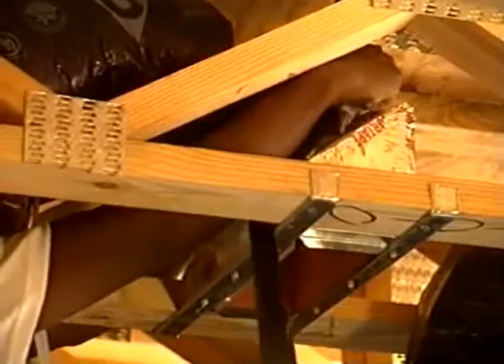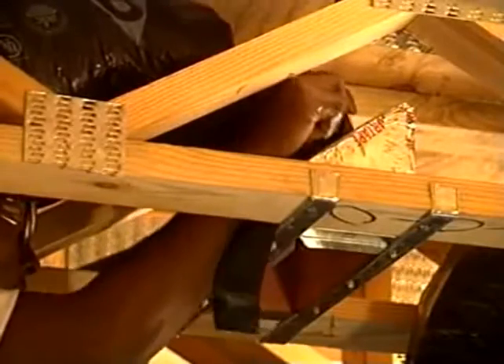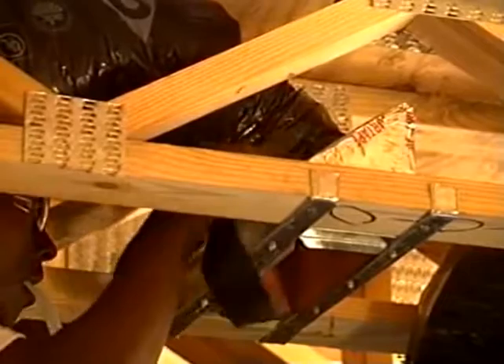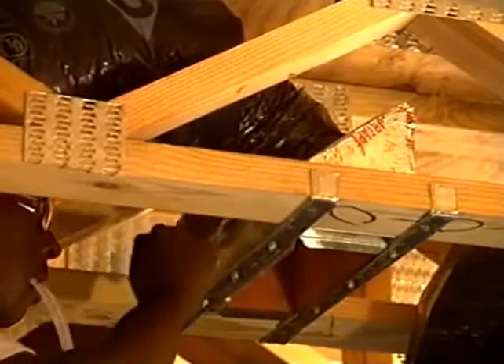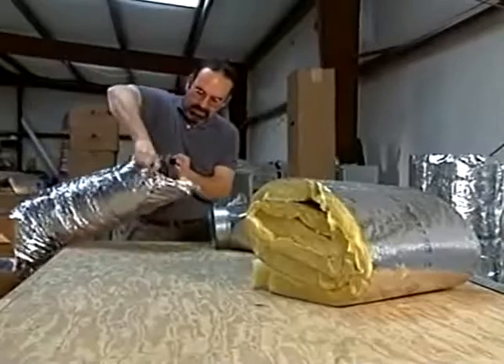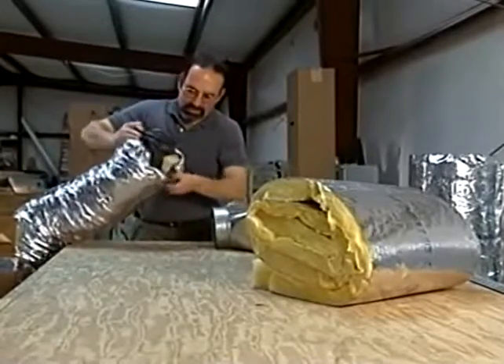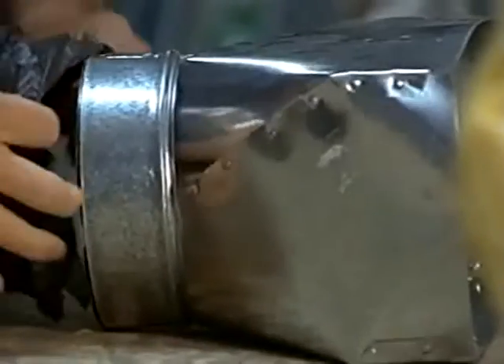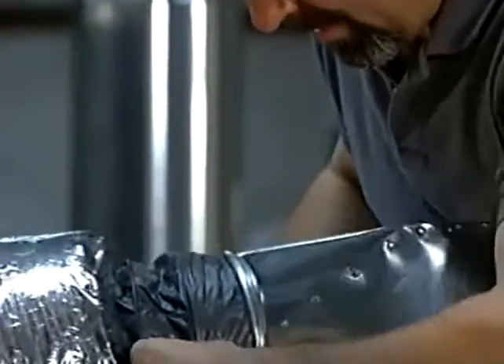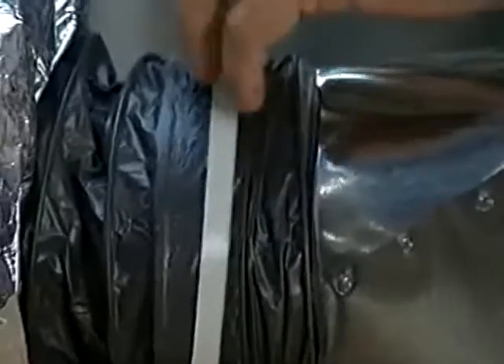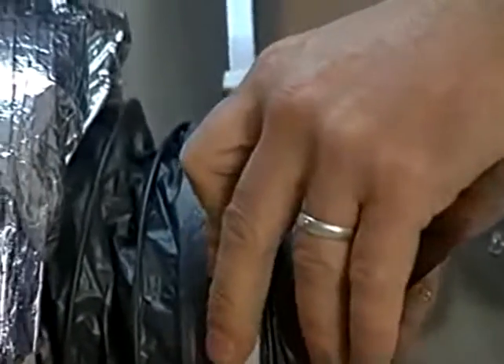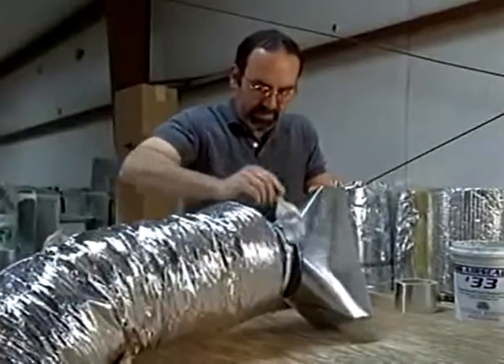Boot and grill connections are also major sources of air leaks and energy loss. Most ductwork contractors install the boot to the ceiling or subfloor first, and then attach the supply line to it, often using only duct tape. Unless this connection is reinforced with mastic, it's difficult to permanently seal the connection this way. A different approach can make the process more efficient and easier on you. This contractor makes all of the boot connections before the job leaves his shop. First, he pulls the insulation down to reveal the inner liner and slides the liner over the metal boot. He secures the liner with a strap or collar tie. He then seals this connection with mastic.